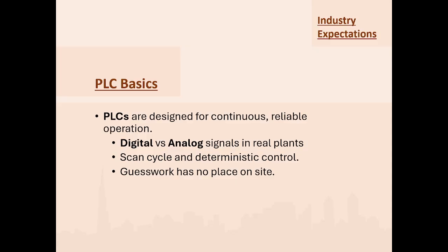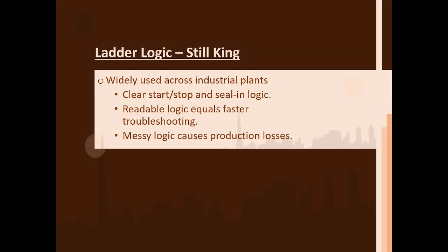A PLC is not a laptop or a desktop computer. A PLC is designed to run continuously, sometimes for years, in hot, dusty, and noisy environments. The PLC works in a repeating cycle called the scan cycle: it reads inputs, executes logic, and updates outputs over and over again. It works with digital signals, which are on and off, zeros and ones, and analog signals, which change gradually. Because the PLC does exactly what it is programmed to do, clarity in logic is very critical. This is why the industry still prefers a particular programming style, which I'm introducing in the next slide, which is ladder logic.